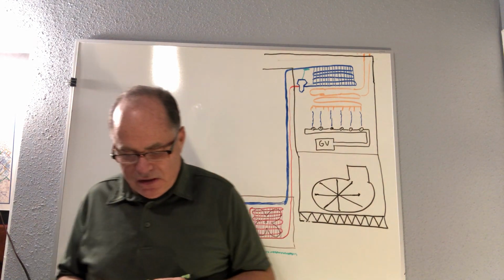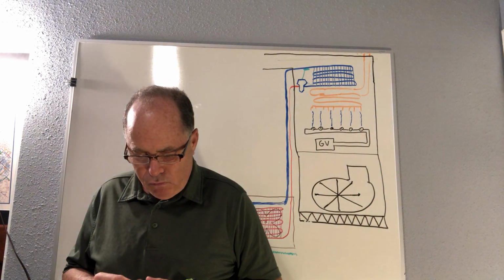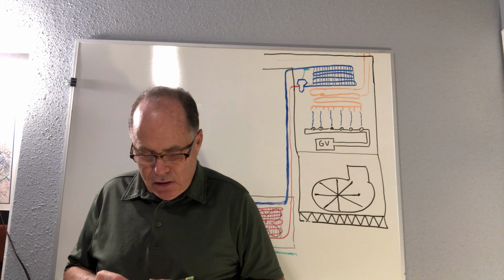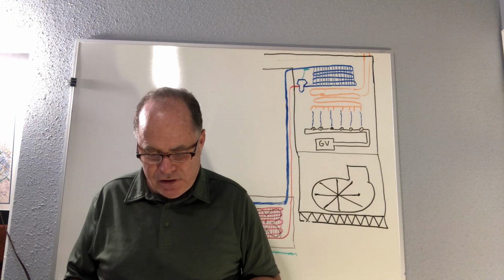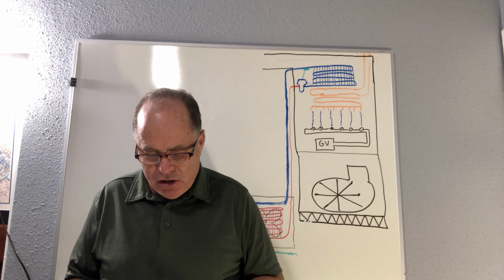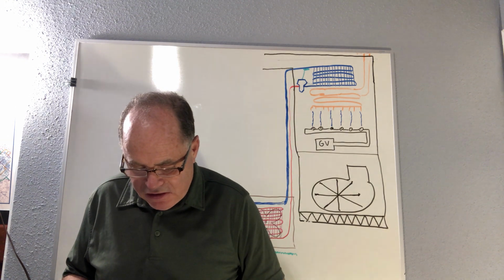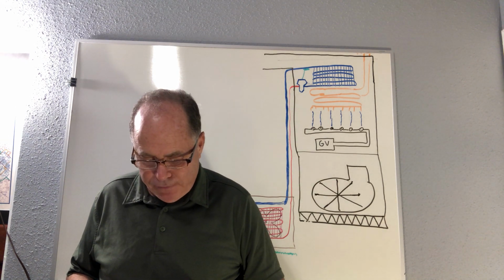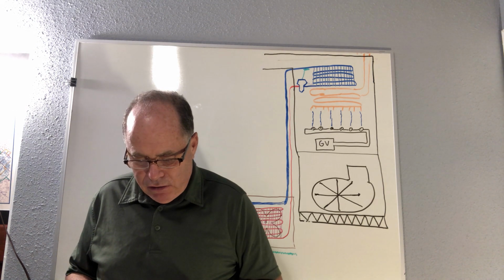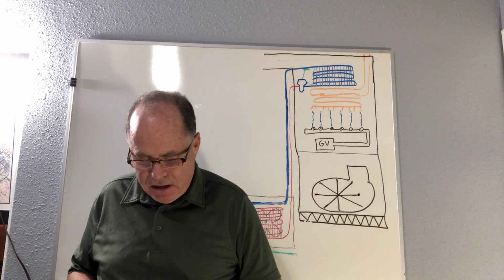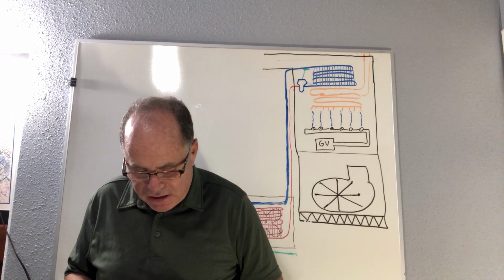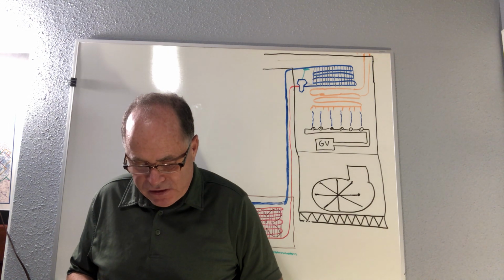On clearances, the lowest portion of the floor furnace, now if you have a floor furnace, shall have not less than 6-inch clearance from the general ground level. Okay? A reduced clearance to not less than 2 inches is permitted, provided the lower 6 inches portion of the floor furnace is sealed. So what we're talking about is floor furnaces.